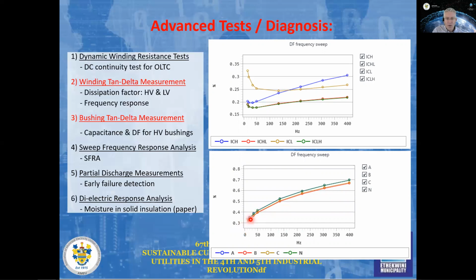And also we can see that these results here are still nicely increasing, which shows that the paper is still very healthy in that bushing. And also all four bushings, in this case we had three-phase bushings and a neutral bushing, were virtually identical, right on top of each other, and very good and very comparable results in this specific case.